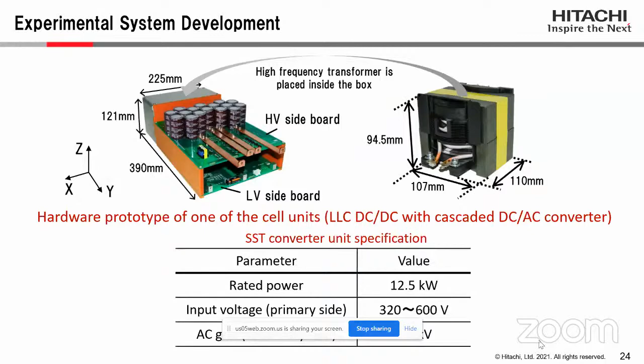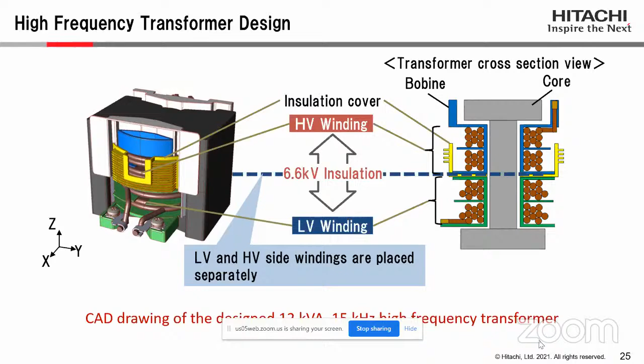Here again is the transformer designed for this application. Since we need high insulation for this type of application, as it is connected to the grid, we used a plate which isolates the primary and secondary sides from each other. There are different design techniques for achieving insulation; in our case we used an insulation plate that separated the primary side from the secondary side.